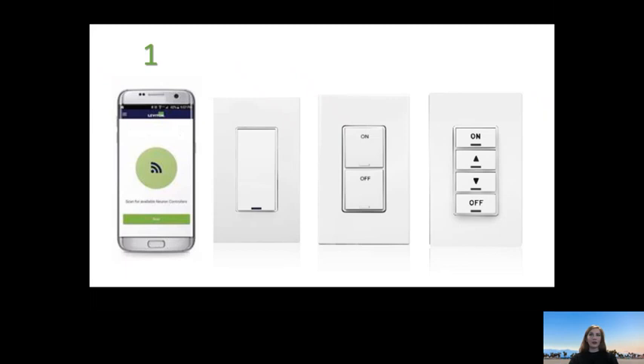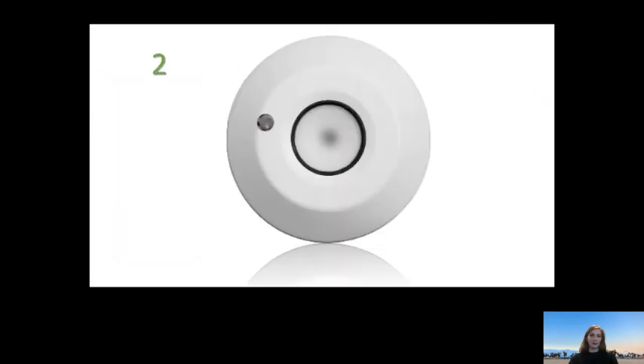The Room Controller app allows you to locate and name your devices. Set your passive, infrared, and ultrasonic device sensitivities. It allows for timeout, auto-adapting, walkthrough, partial on, and partial off settings. You can choose between auto on, auto off, or manual on, manual off. You can adjust your dimming, demand input response levels, and your HVAC and plug load controls from the app as well. The flexibility of the Room Controller app makes commissioning in the field flexible, easy, and user-friendly, eliminating a need for costly third-party commissioning expenses that don't always fit into the project's budget.